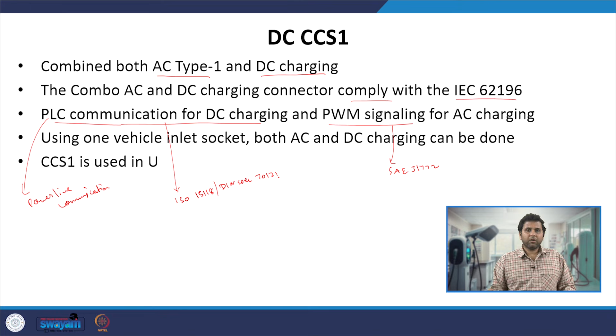It uses PLC communication, which is power line communication, for DC charging, and the PWM signaling, which follows the same SAE J1772. When they are doing the power line communication for DC charging, the communication standard is given in ISO 15118 or DIN SPEC 70121. In ISO 15118 the high level communication protocols are defined, and in IEC 61851 aspects related to different charging stages, charging states and sequences are included. Thus, these standards define protocols for high level communication, because a lot of information needs to be exchanged while doing the communication. And when they are doing the AC charging, it is SAE J1772.